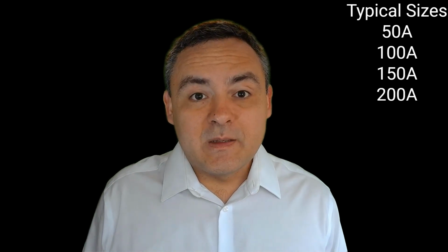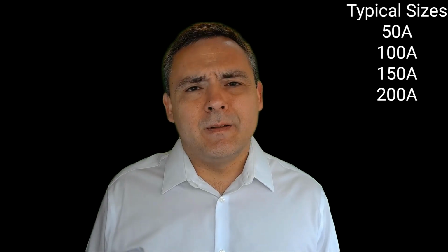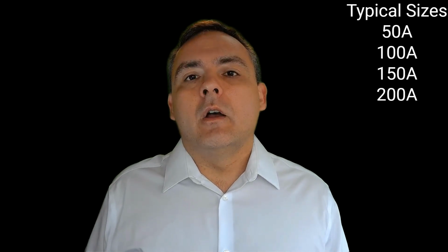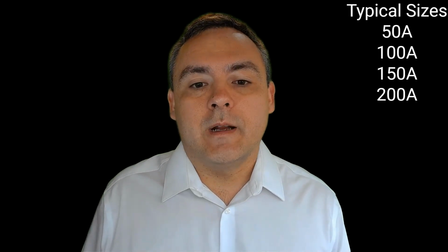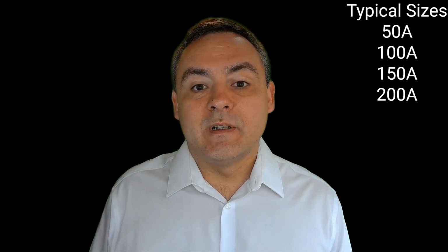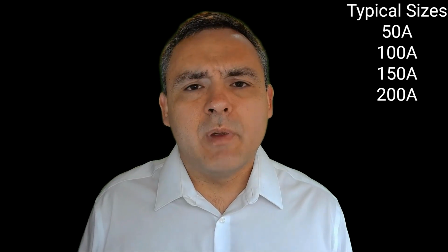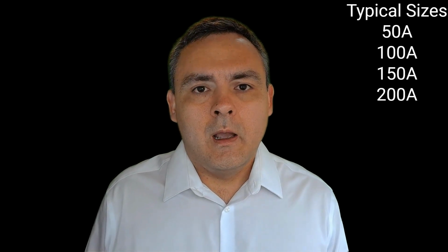Active harmonic filters are sized based off voltage and current. They will usually specify how many harmonics they can cancel out. The ones that I have specified in the past come in increments of 50 amps. That is 50 amps, 100 amps, 150 amps, and 200 amps. If you need more compensation current, then you can usually parallel them. I usually size them with power system analysis software.